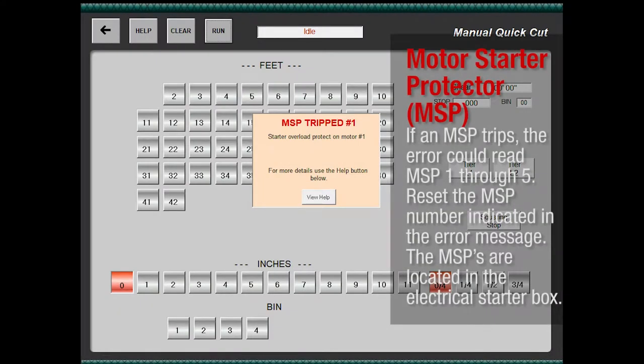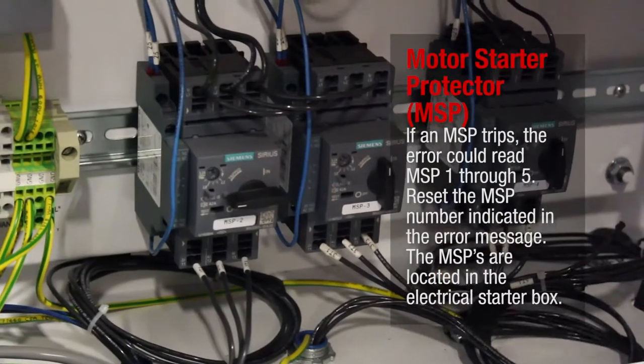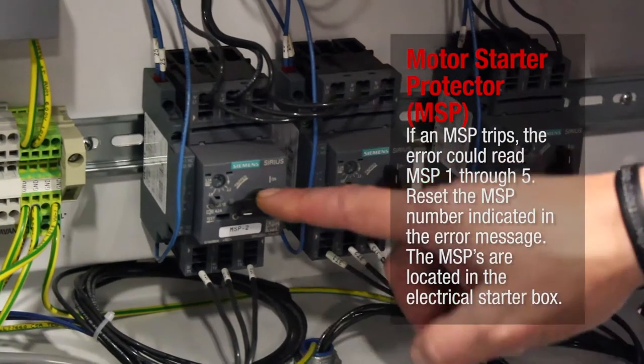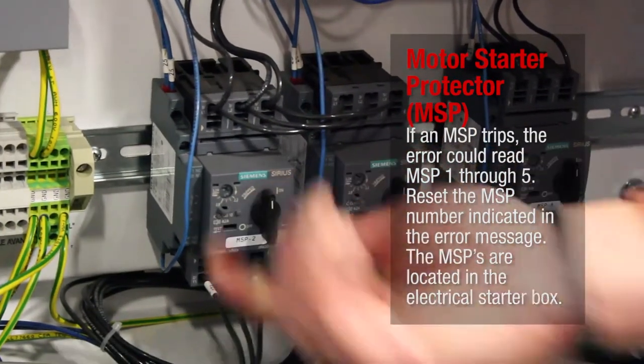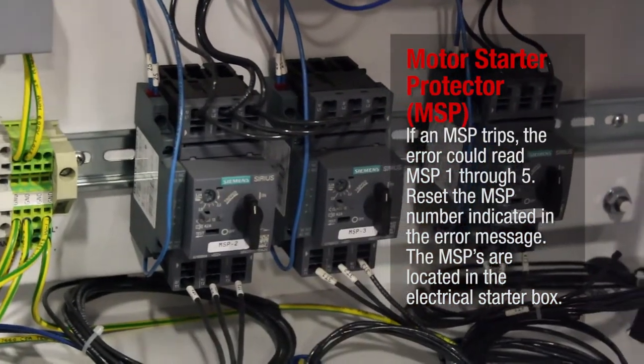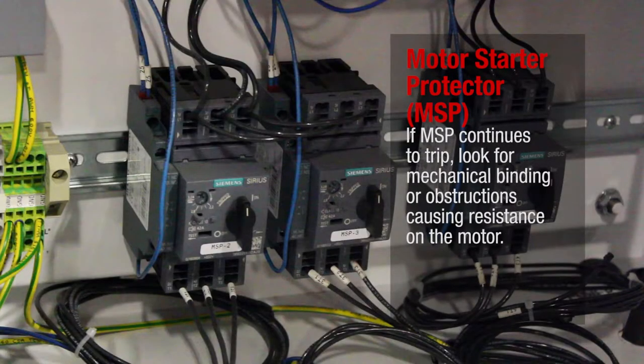Motor Starter Protector, MSP. If an MSP trips, the error could read MSP 1 through 5. Reset the MSP number indicated in the error message. The MSPs are located in the electrical starter box. If the MSP continues to trip, look for mechanical binding or obstruction causing resistance on the motor.